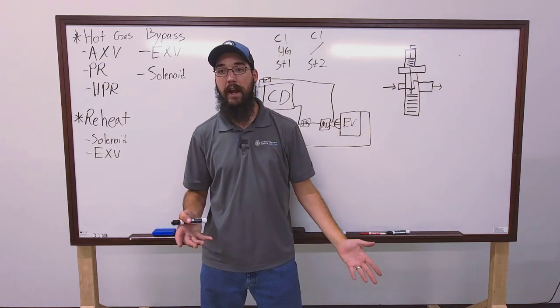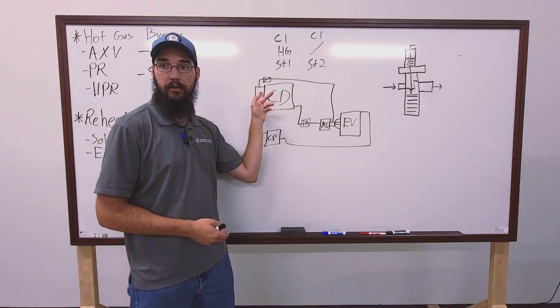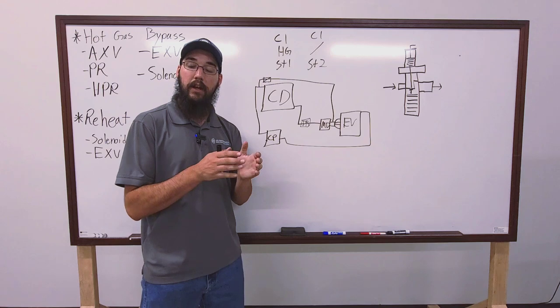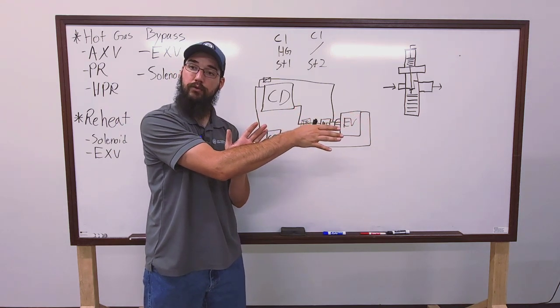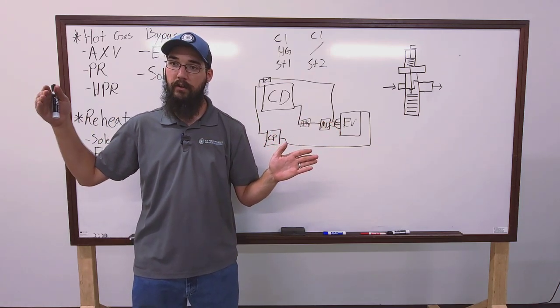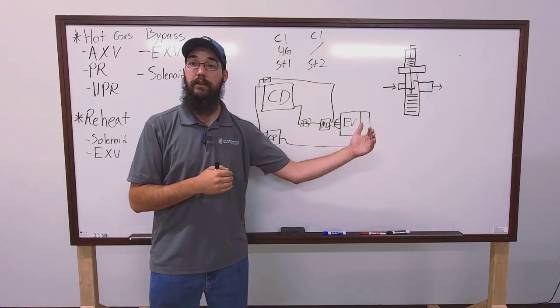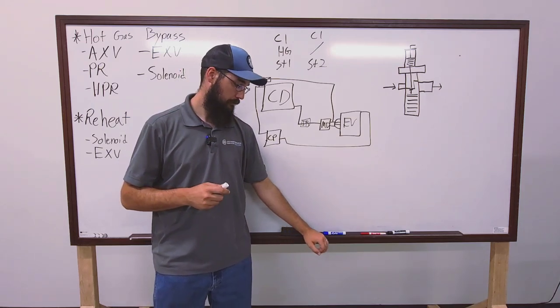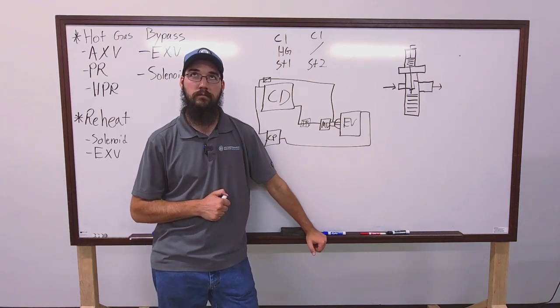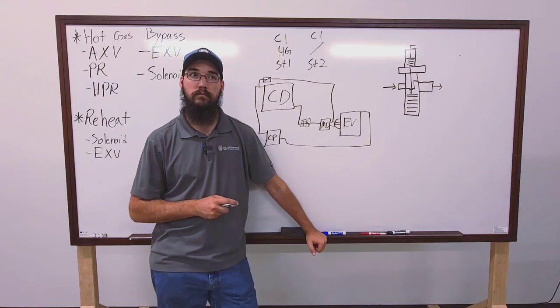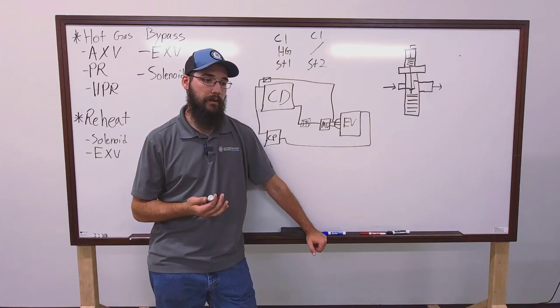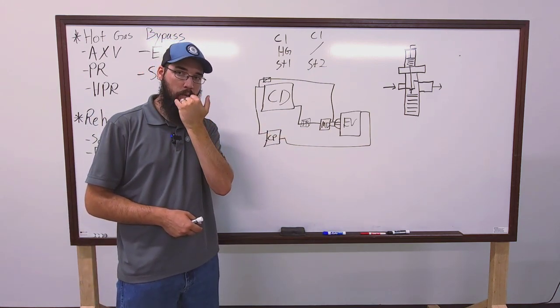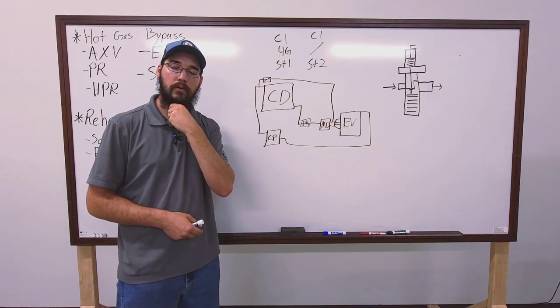And that's if you get the 150 coming in. If it's truly not flowing at all, both sides of that line are going to stay ambient, unless this valve is super close to the discharge. Like carriers. Carriers, I think, right next to the compressors. Yeah, yeah. If it's within just a couple of feet of the physical discharge line, then, yes, you're going to see the temperature just radiate through that pipe. That is true. But you go down that pipe a little ways, you know, say several more feet, and you're going to find that that temperature didn't stay consistent, but it should have. Forgive me if I'm wrong. The carrier, the large carrier RTUs, their hot gas bypass is pretty close to the compressors. I would say the building I'm thinking of.